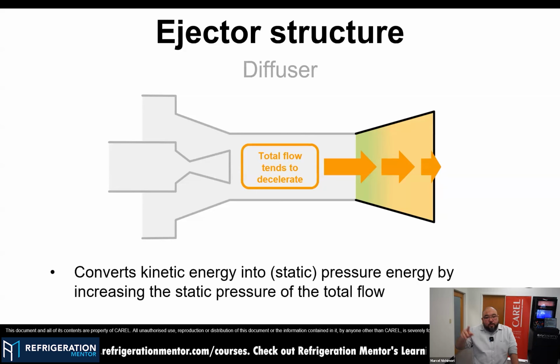And you might be asking, what is the advantage of making this compression? I mean, why should I increase the amount of gas that I'm putting inside the liquid receiver, right? So the point here is that you could use some piping diagrams, I will show you later, to make the compression not from the compressor perspective, not from the suction at MT 400 psi, but from the liquid receiver perspective. So all your compressors will be working as parallel compressors. So you have a higher suction pressure, same discharge pressure, we cannot change that, right? So since the compressor pressure ratio is decreasing, the amount of energy that you need, or mainly the number of compressors that you need to have on to make that compression, can be reduced. So that's where the energy savings come from, because I'm getting refrigerant at higher pressure to the compressor, so the compressors will work less to make the compression.